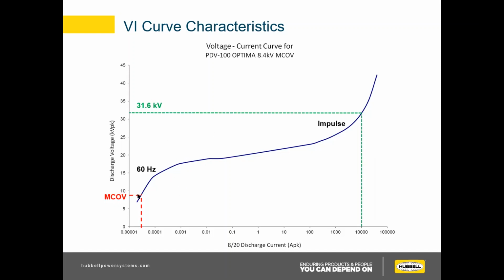And so on the other end of the spectrum, we have our impulse. So that's a switching surge or a lightning impulse. And so we're at 10,000 amps right here. And so our discharge voltage, like we said earlier, is about 31.6 kV. The reason we can conduct all this current here is because it's such a short amount of time, in the microsecond range, super, super short. This region is not temperature sensitive. It really doesn't matter, like I said, because it's so short. And then our impulses can go on up from there, up even higher.